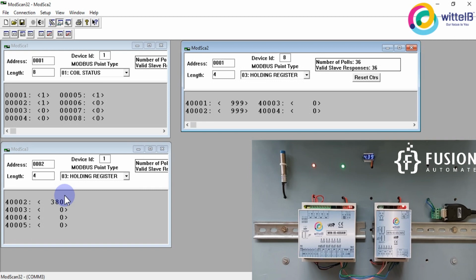Now, if you want to operate this digital output, the coil numbers for this digital output are from 1 to 4: 01, 02, 03, 04. So these 4 coils are associated with the digital outputs of this channel. Digital output 1 is associated with 01, digital output 2 is associated with 02, digital output 3 is associated with the 03 coil status, and 04 is associated with the DO4 of this card.